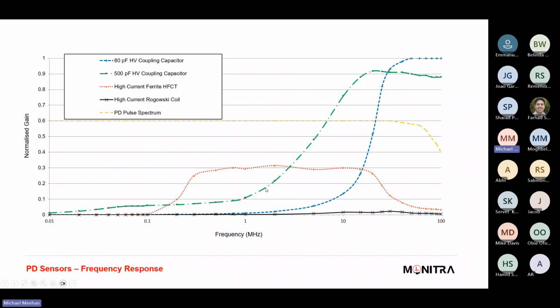If we think of the frequency response, or where the PD signals sit, based on IEC 60270, the frequency band that best determines PD activity in a machine sits between 40 and 800 kilohertz. So with the technology you'll find on the market, typically the coupling capacitors are of these ranges. 500 picofarads we think is a very useful capacitance value. That's what we use, and obviously the high frequency CTs.